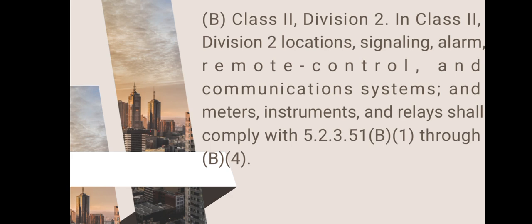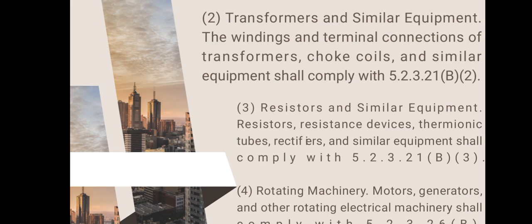So for the general requirements applicable to both Class 1 and Class 2 locations, grounding and bonding: wiring and equipment must be grounded as specified in Article 250. Locknut-bushing and double locknut types of contact shall not be depended on for bonding purposes. For sealing, where a raceway provides communication between enclosures with different protection requirements, sealing is required to prevent the ingress of hazardous materials. For the surge protection, surge arresters and surge protective devices installed in a Class 2 Division 1 location shall be in suitable enclosures.